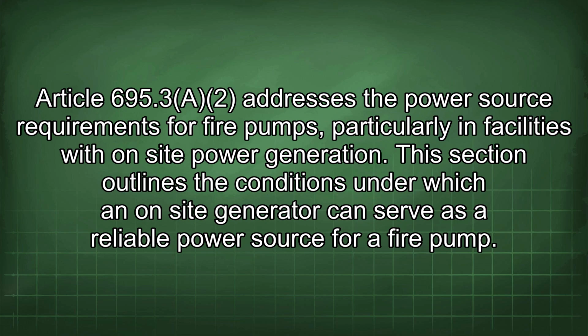Article 695.3 addresses the power source requirements for fire pumps, particularly in facilities with on-site power generation. This section outlines the conditions under which an on-site generator can serve as a reliable power source for a fire pump.